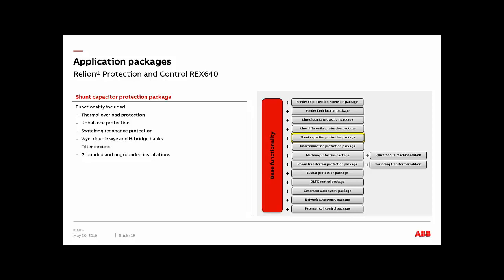And as I mentioned before, for the filter circuits, you can also have capacitor bank switching resonance protection for these circuits as well. So you can protect against damaging harmonics in these applications. That's going to be for your shunt capacitor bank protection package.